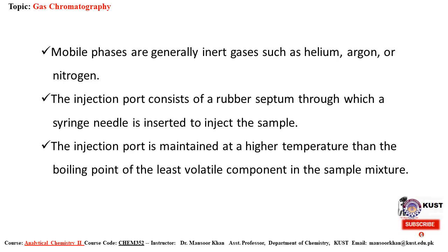As we have already mentioned, in gas chromatography the sample is needed in its volatile form. So the temperature of the injection port must be higher than the boiling point of the sample which is injected, because we need the sample to be in its volatile form.